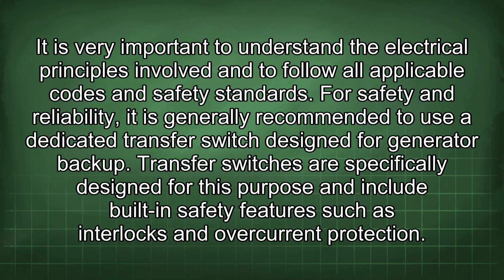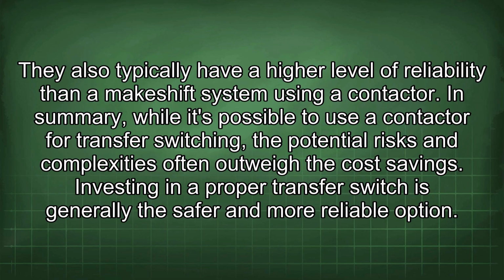For safety and reliability, it is generally recommended to use a dedicated transfer switch designed for generator backup. Transfer switches are specifically designed for this purpose and include built-in safety features such as interlocks and overcurrent protection. They also typically have a higher level of reliability than a makeshift system using a contactor. In summary, while it's possible to use a contactor for transfer switching, the potential risks and complexities often outweigh the cost savings. Investing in a proper transfer switch is generally the safer and more reliable option.